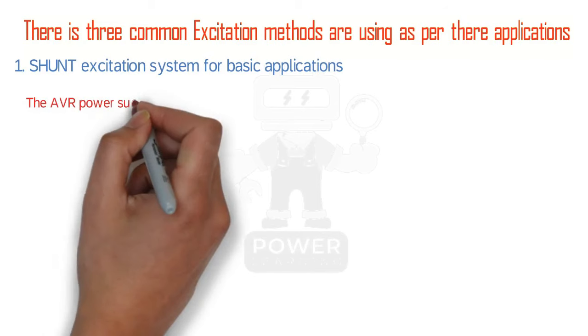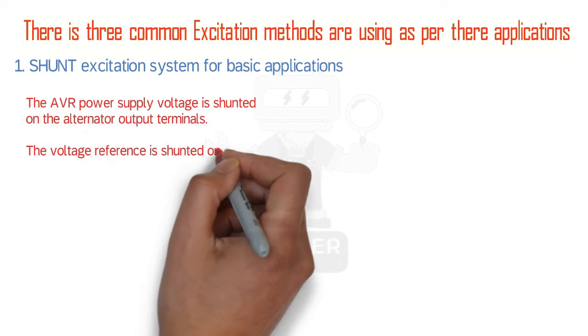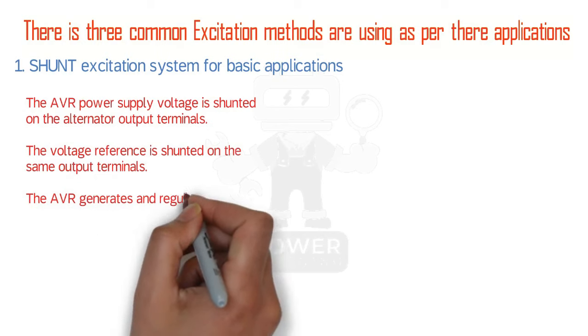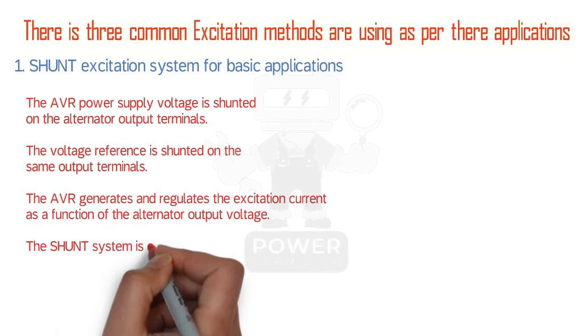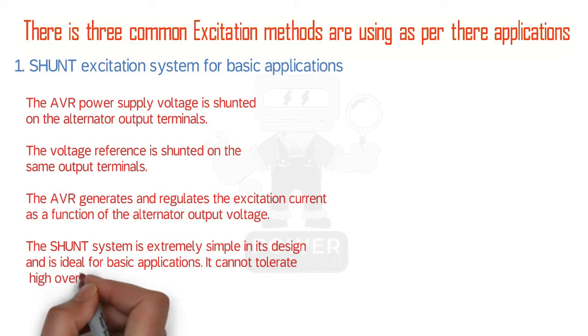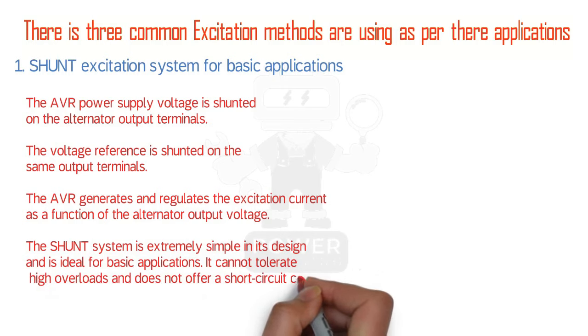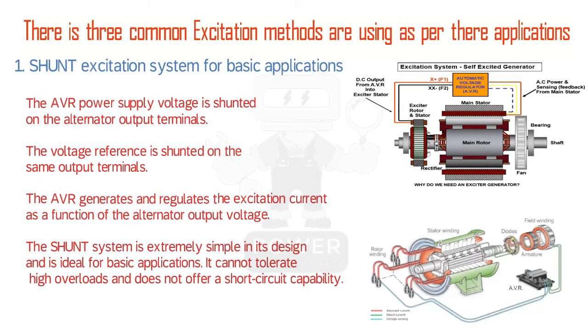In the shunt excitation system, the AVR power supply voltage is shunted on the alternator voltage output terminals. The voltage reference is shunted on the same output terminal. The AVR generates and regulates the excitation current as a function of the alternator output voltage. The shunt system is extremely simple in its design and is ideal for basic applications. However, it cannot tolerate high overloads and does not offer short circuit capability. Here you see a simple diagram of a self-excited generator.